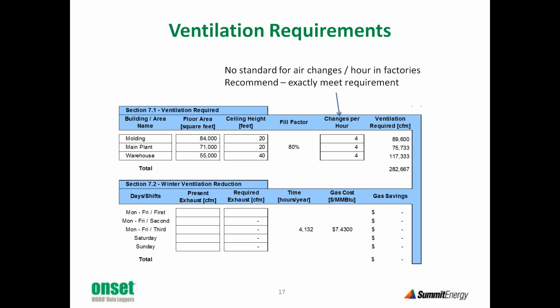So I can calculate the volume enclosed by the building, and I use a factor of 80% because the building has other things in it besides the air. It has people and equipment. So we use a fill factor of 80. In this particular example, I start with 4 air changes per hour, and that tells me that my ventilation requirement is 282,667 CFM. So that's a place to start.